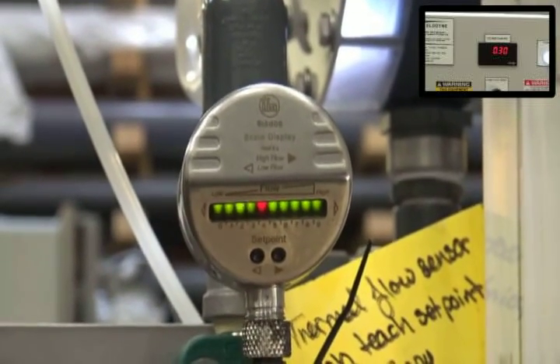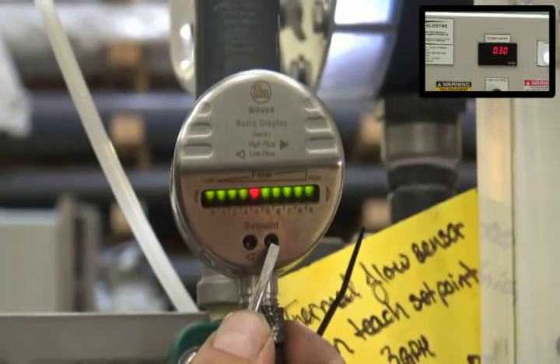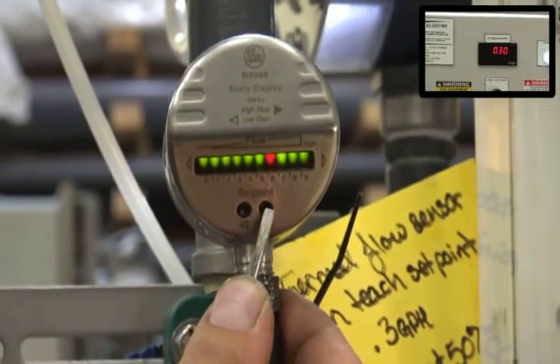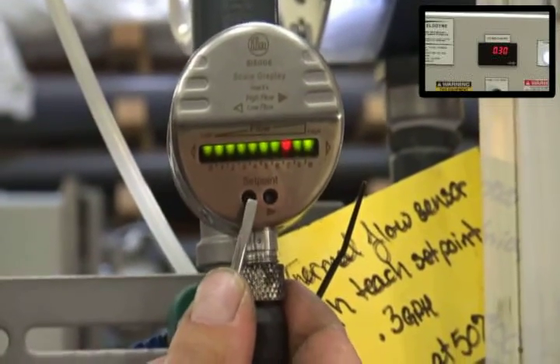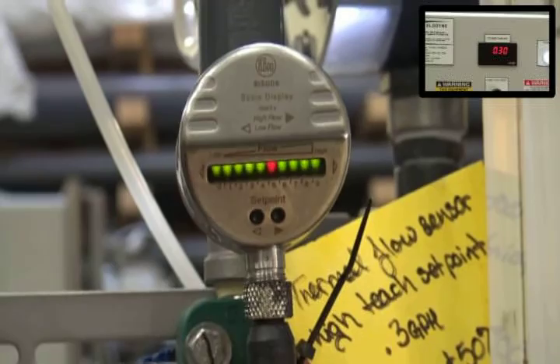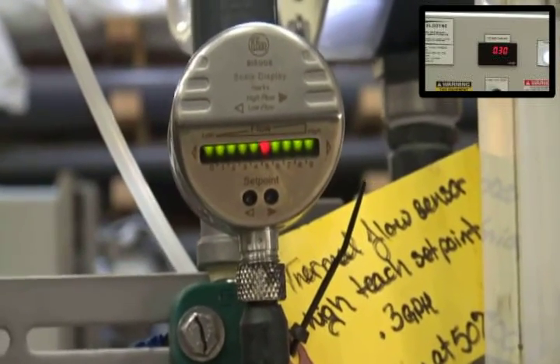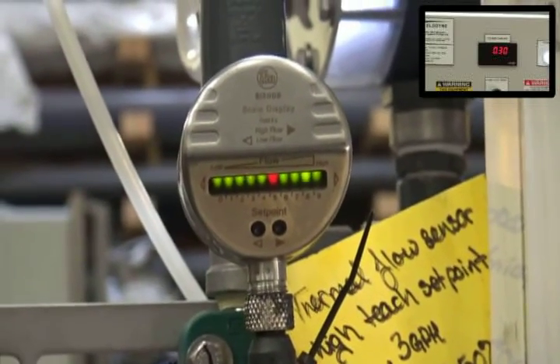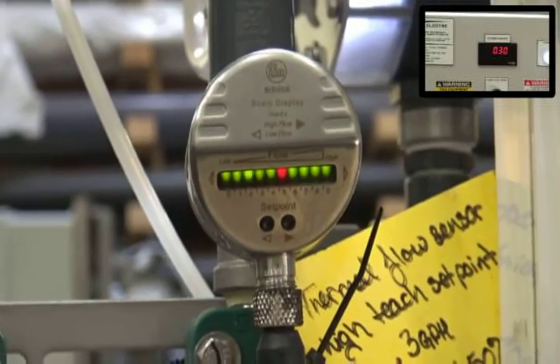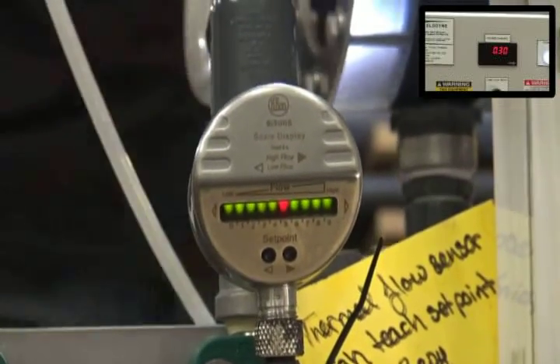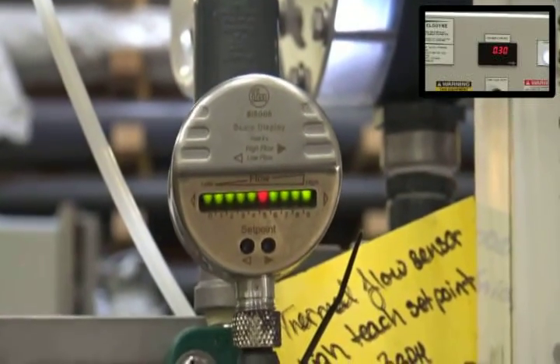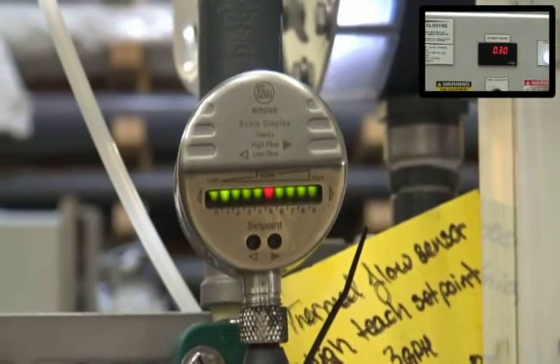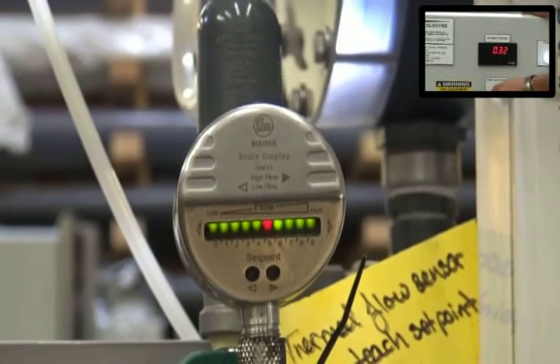Now we can fine tune that switch point right now by just tapping the buttons back and forth. When you get it from the factory, it will be set to the number 5 spot, which is about 50%. So now we can actually turn this thing down to our 20 turn down point, which is going to be a 0.15.